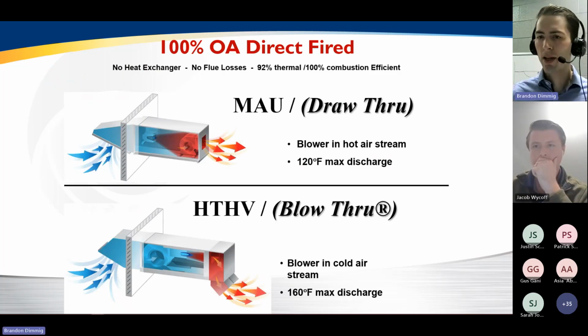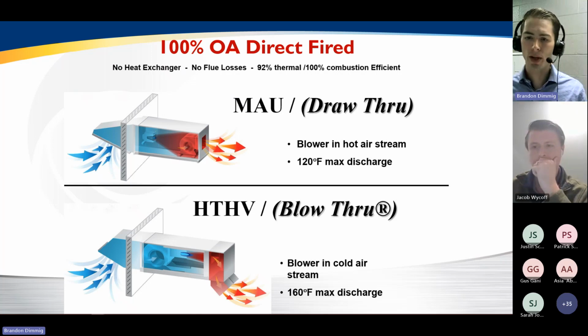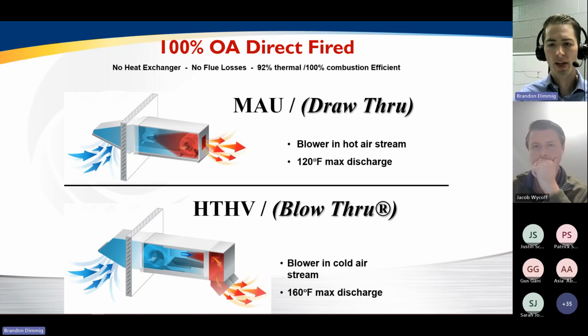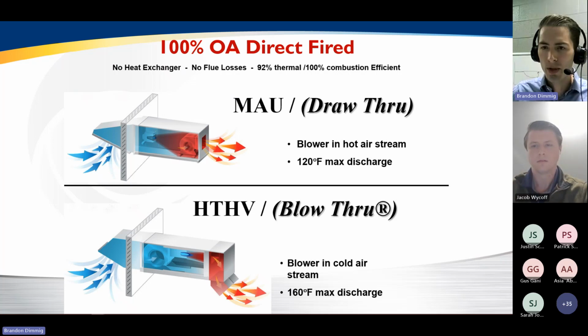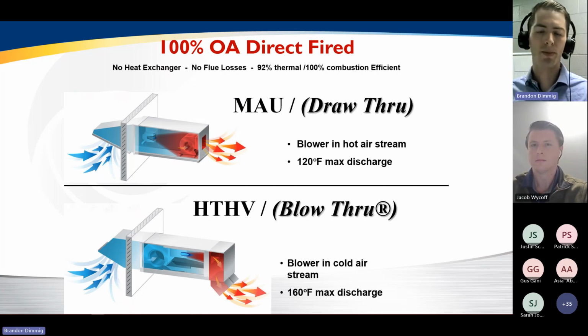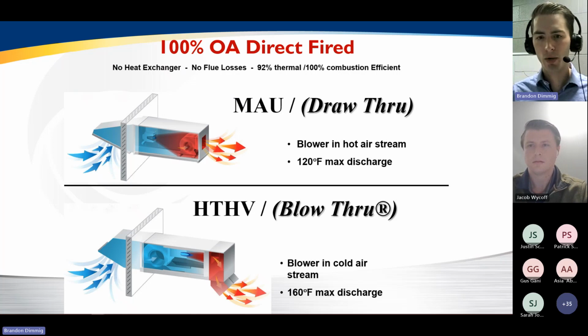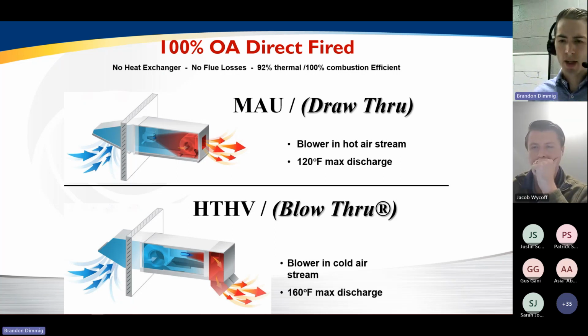So I want to make clear a distinction between a traditional makeup air unit and an HTHV unit. And it really has to do with the orientation of the blower and the burner. Perhaps you are more familiar with a traditional makeup air unit in which the blower is in the warm or the hot air stream, drawing air across the burner. And that's what you see in the top image there. The discharge temperature of these units is limited just by the practical thermal limitations of the equipment in the hot air stream. And this is opposed to a blow-through unit or an HTHV unit in which the blower and the motor and those critical components are in the cold air stream, blowing air over the burner. And so you can see that distinction.